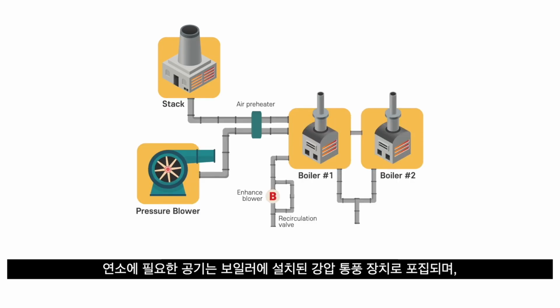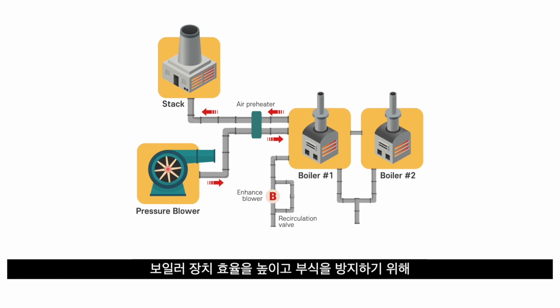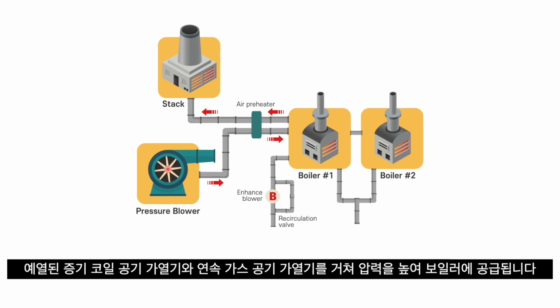Air required for combustion is captured with forced draft equipment installed in the boiler, increased in pressure, and supplied to the boilers after preheated by passing through steam coil air heater and continuous gas air heater to increase boiler efficiency and prevent corrosion.